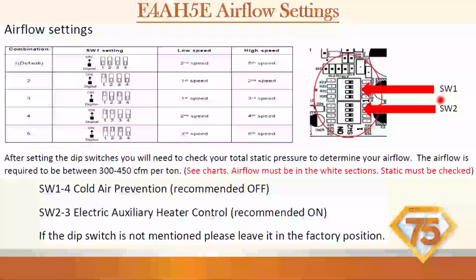So again, here's those SW1, SW2. We get our airflow settings and take out some of the guesswork, right? You do need to take your static pressure of the unit. After setting the dip switches, when you adjust these dip switches, it does have to be off. Power down the system. Make sure it's off. Switch your dip switches. Turn it back on. You need to check your total static pressure to determine your airflow. The airflow required is 300 to 450 CFM per ton. Again, we're trying to get to 400 CFM.